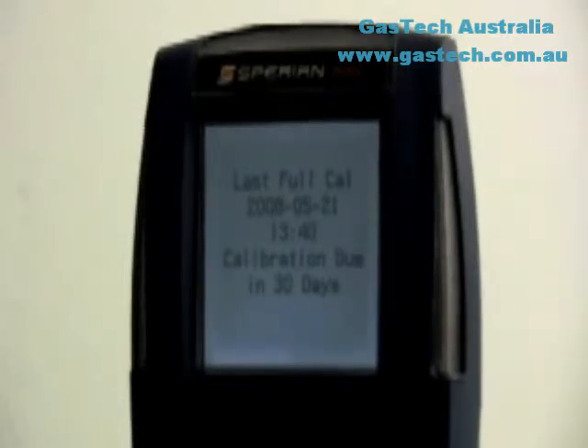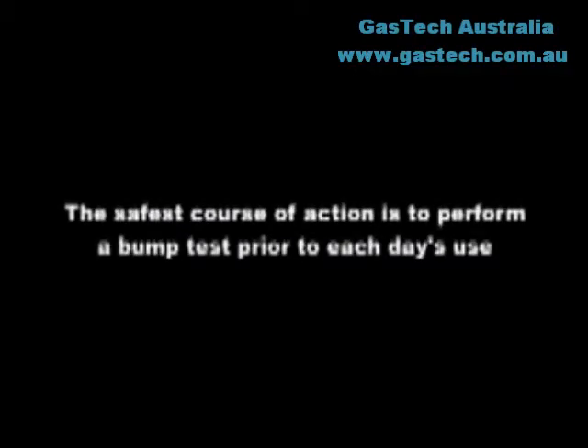Sensor response in the PHD6 can also be verified using the IQ6 Express docking station. Just drop the PHD6 into the dock, and the dock will automatically perform a bump test and assess the critical functions of the instrument, all in about 30 seconds. If the bump test fails, the dock will perform a full instrument calibration without intervention from the user.